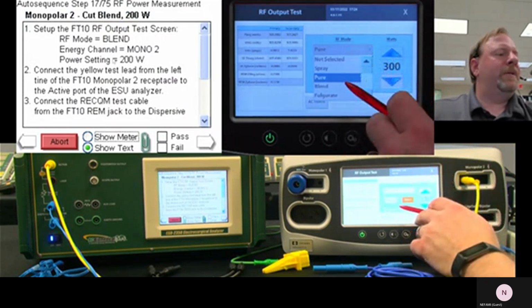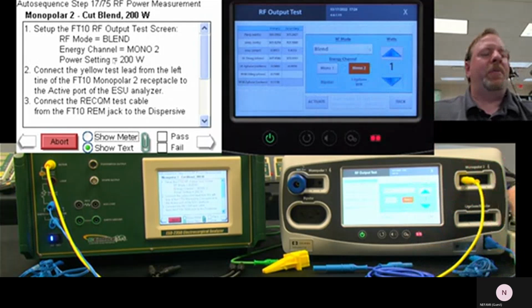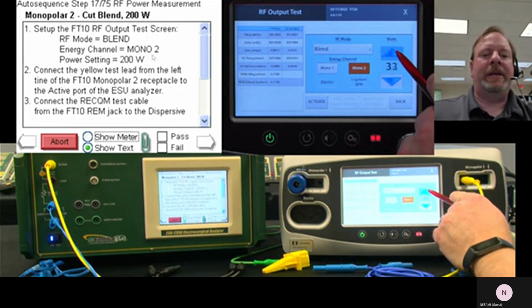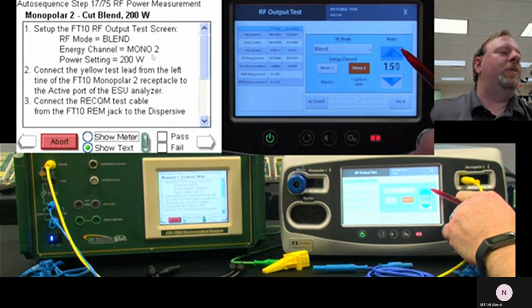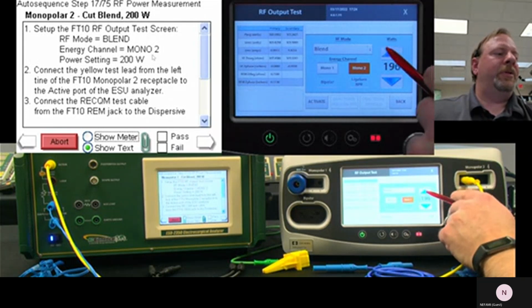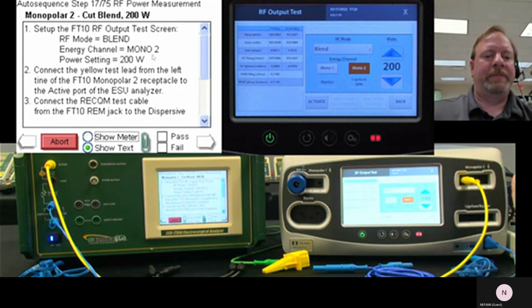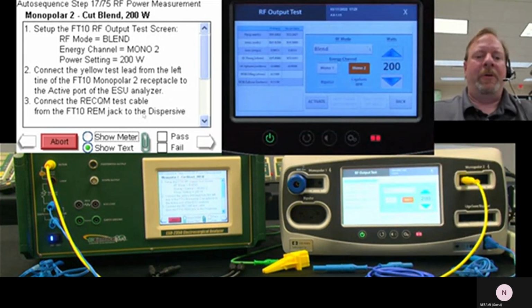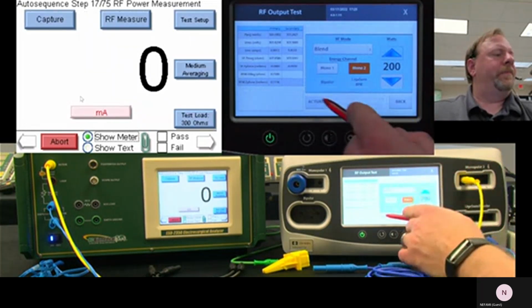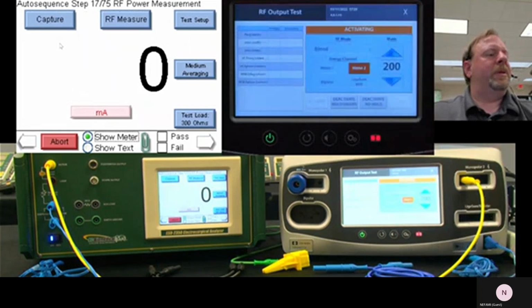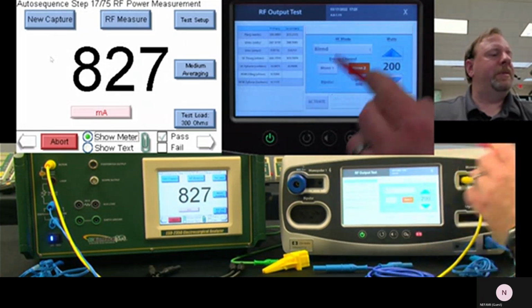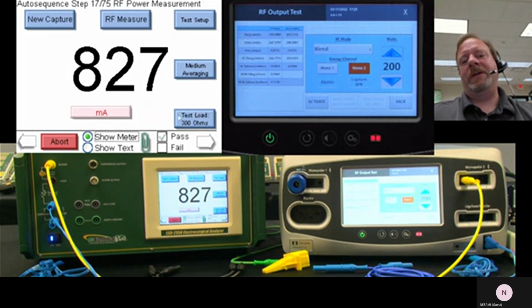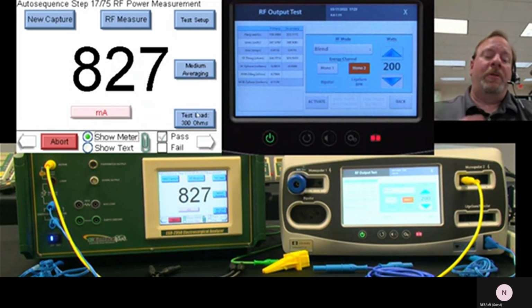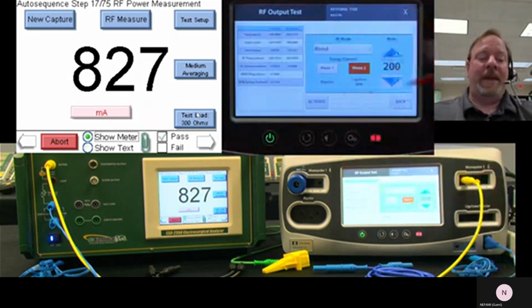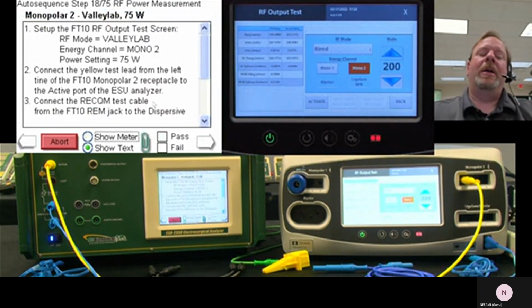So if you notice in the service manual, they have you test every port and just about every setting, not every setting, but every mode on this generator. What they're doing is making sure that all of the modes work, all of the ports work, different power levels, that sort of thing. So we're just going to walk through this process here: capture, deactivate, and move on to the next. Now you'll notice also this load, it's all pre-programmed into the auto sequence. The 2350 automatically sets itself to the load that's required per the service manual from Covidien.